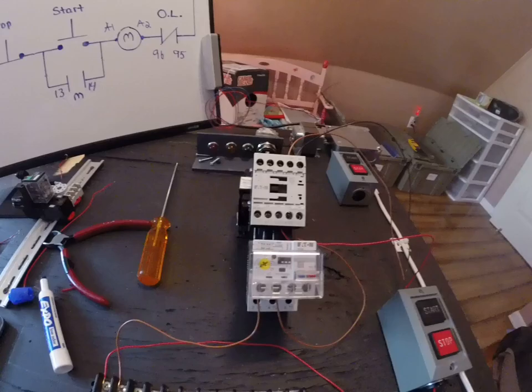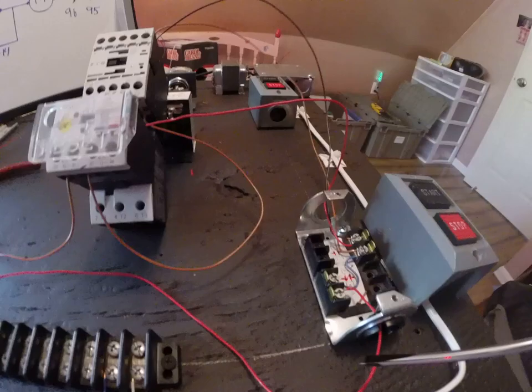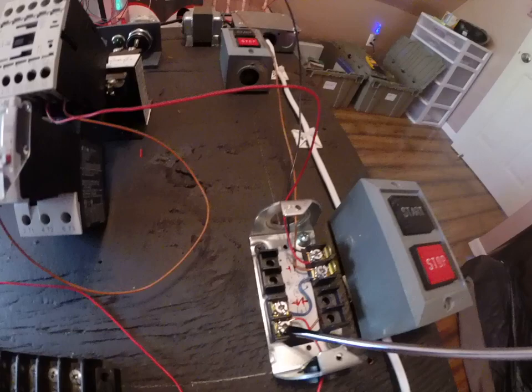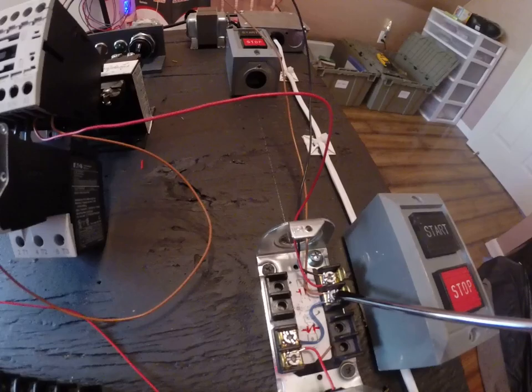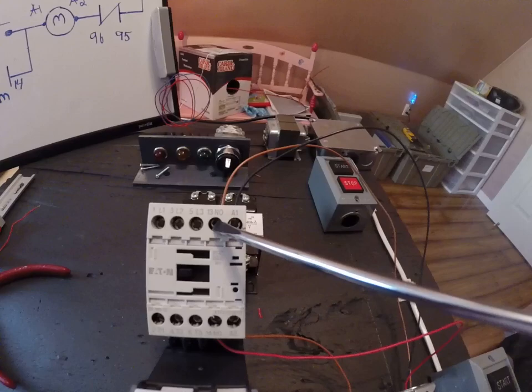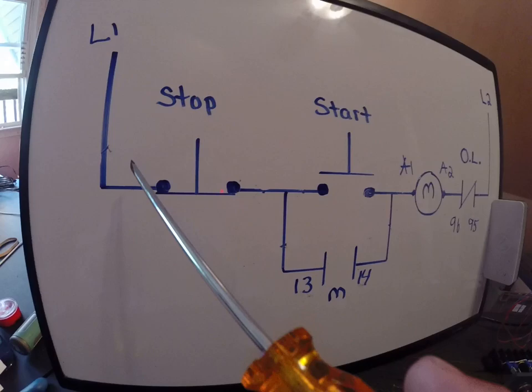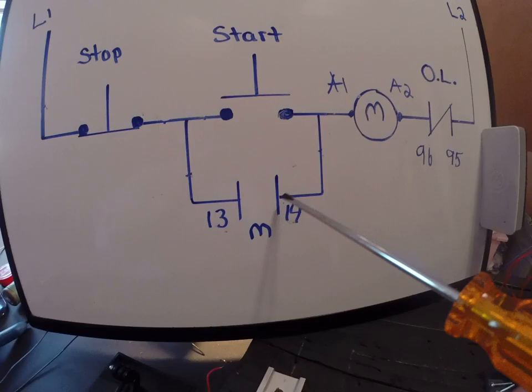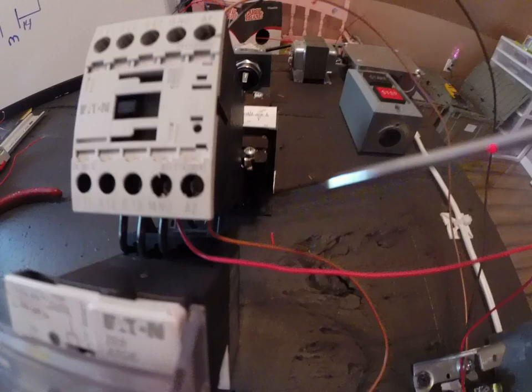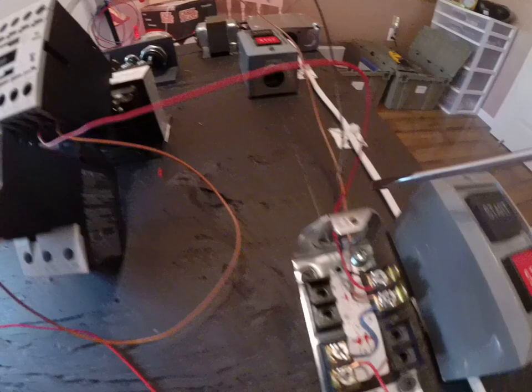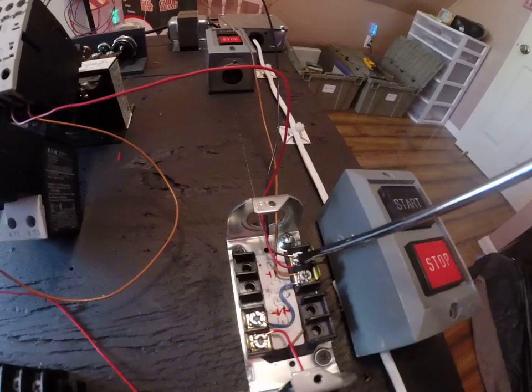But if you trace the wire out, it's very similar circuits with the one we did yesterday. Looking at your diagram, you've got a feed to the stop, you've got your internal jumper going to your start, off that same screw of the start button we come all the way up to our normally open contact for our holding circuit, and that's represented by this, this and this. Then I come off the other side of that open contact back to my switch, I come off the other side which is underneath here - the other NO, I come off the other side of it in red back to my switch, of course my start button.